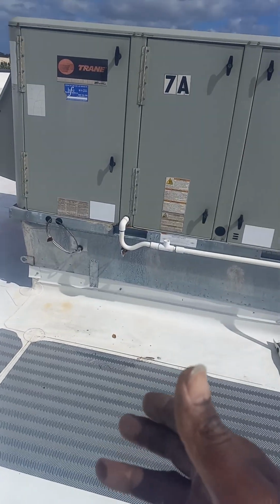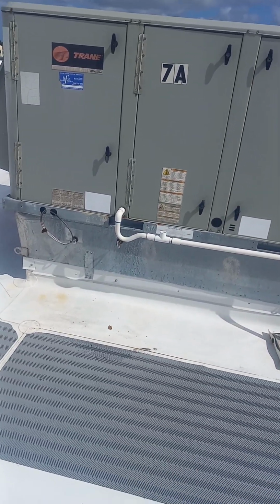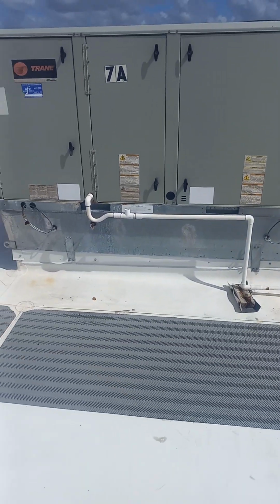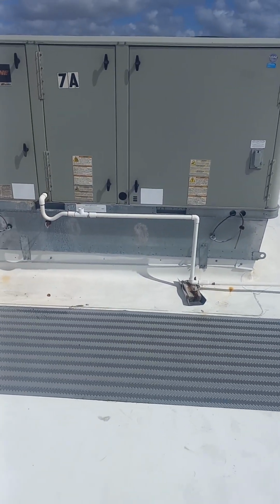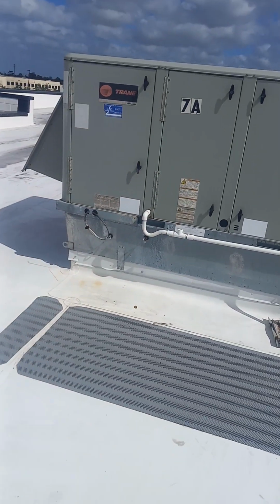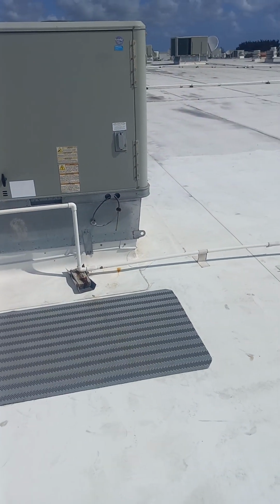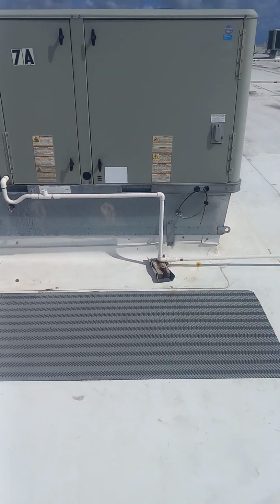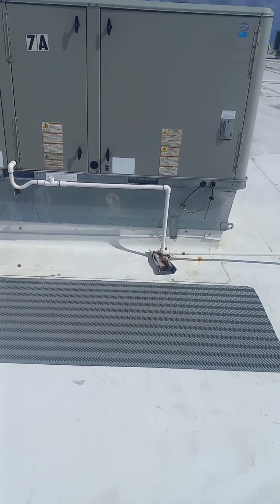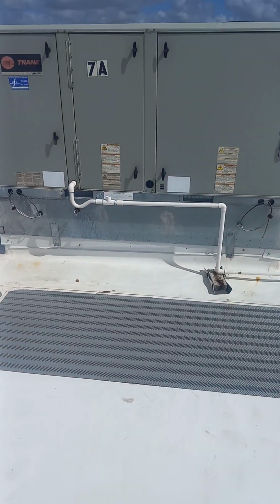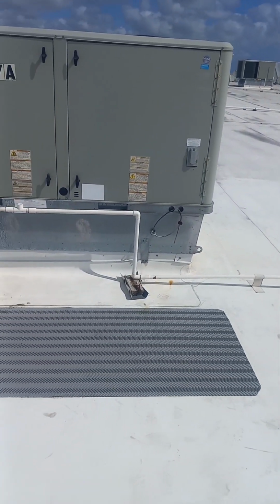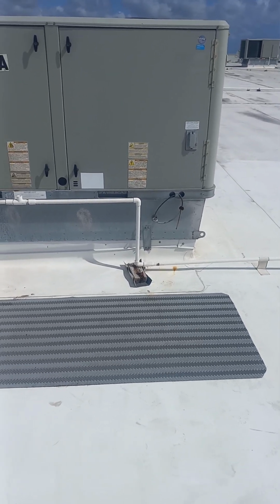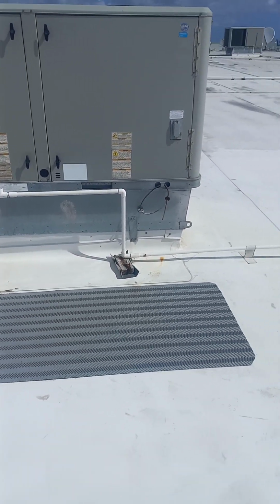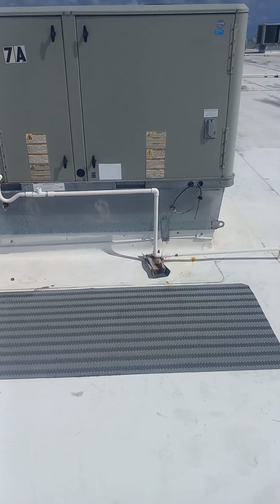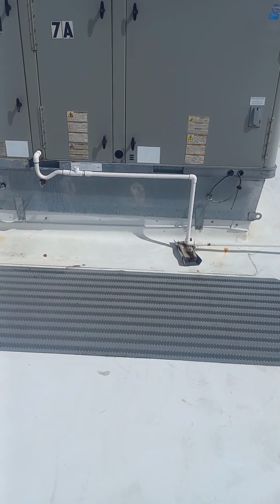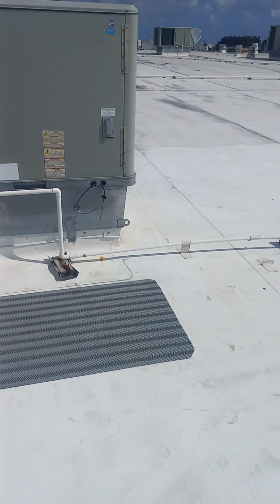So you have a supply ductwork that goes down, return ductwork that goes down. A lot of people use metal depending on the application. So you have metal, or you have fiberboard. Fiberboard is the flexible one, metal is much harder. But even if you use sheet metal, you still have to insulate it, especially if you're in a high humidity area. That unit can sweat and have a lot of water in the building, dropping on the ceiling and messing up a lot of stuff. So in a high humidity area, they use insulation on whether it's ductboard or metal.